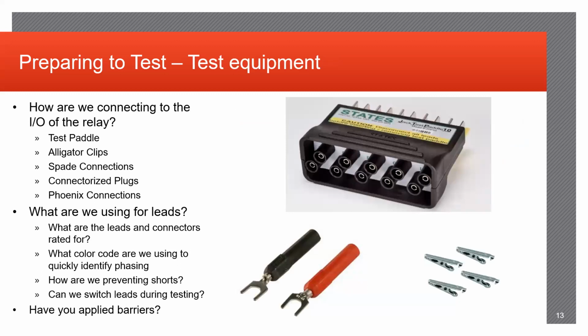Again, going over some of the different types of test equipment when you're setting up. This is an older test paddle, one of these States paddles that plug directly into the knife switches. This back piece is where it will be inserted, and the front panel is where you'll be connecting your test leads straight from the test set. It's extremely convenient compared to alligator clips, which can cause shorts between circuits. That's not only dangerous, but can also damage the relay itself, which will be a big no-no to the client. So if you are using alligator clips, make sure that they are insulated and properly separated from each contact point.